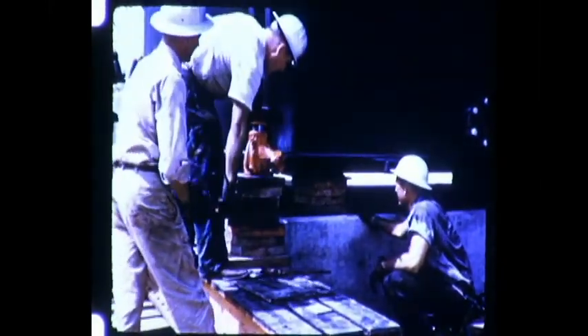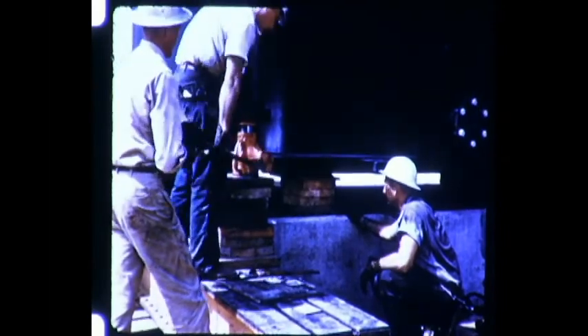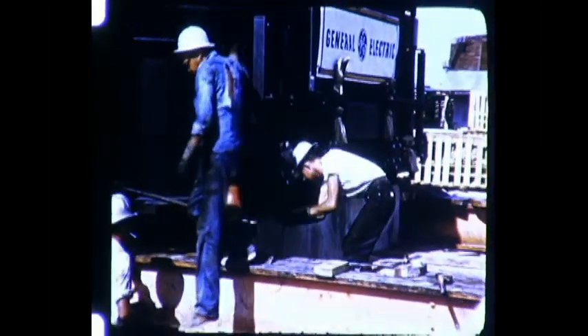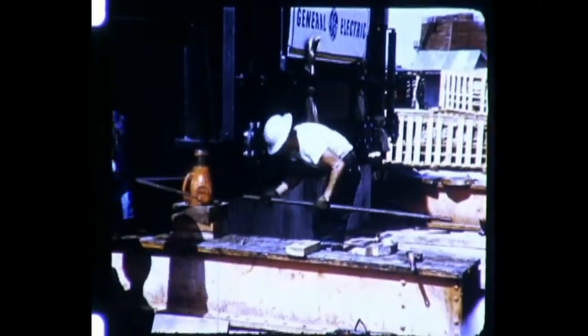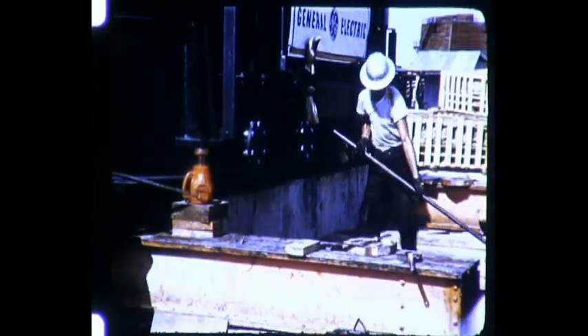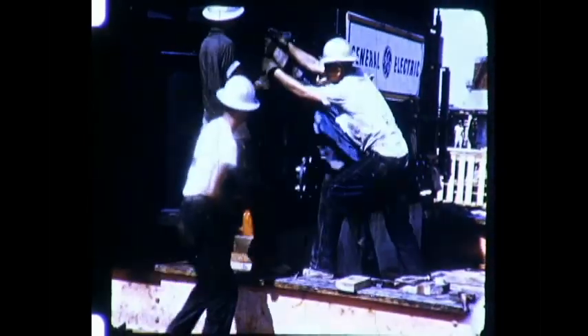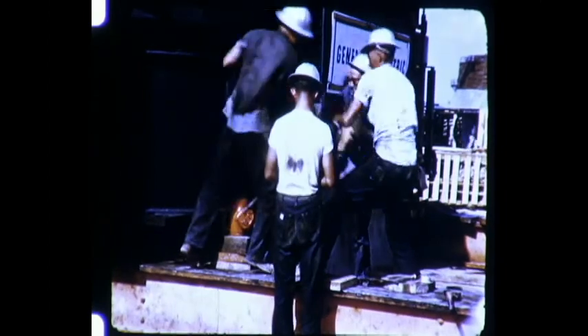Now the unit is jacked down until only some small adjustment rods lie between the transformer and the footings. The rods are used to permit lateral alignment of the transformer, and after their removal, the transformer is jacked down for the last time. Chisel marks near the top of the tank permit easy centering of the unit on its footings.